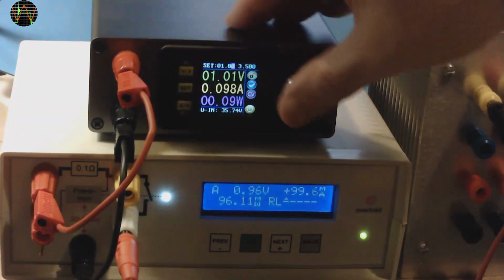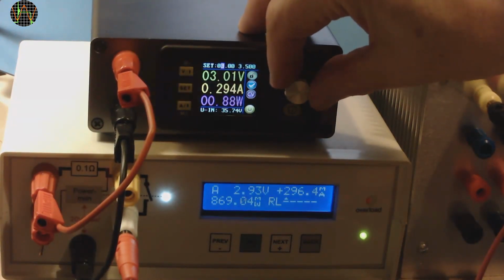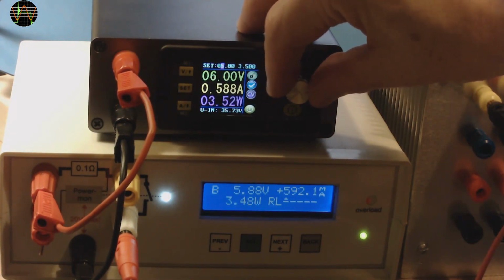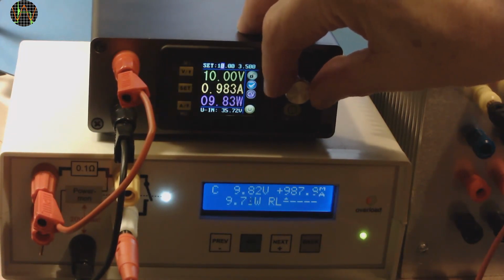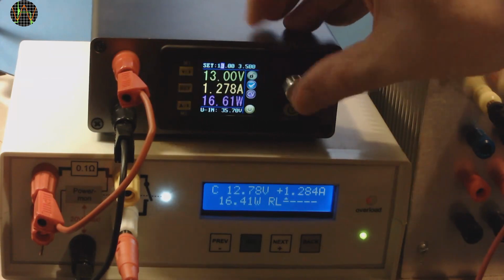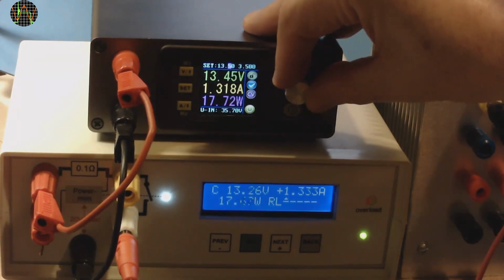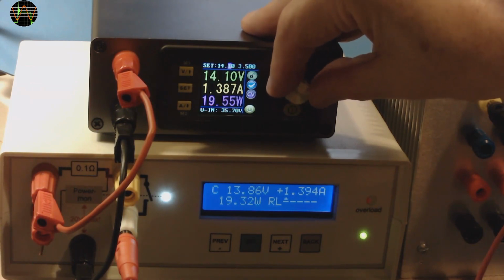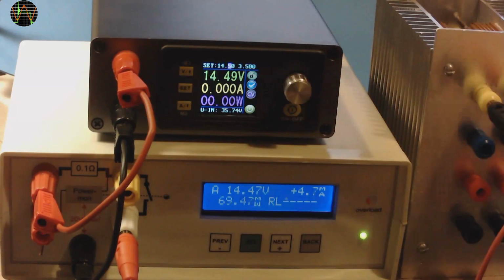I'm now increasing the voltage. The difference in voltage between the power supply and the power mon are due to voltage drops, and as the L in the status shows, power mon is currently configured to measure the voltage over the load, not the supply. There, the relay triggered. I was a bit hasty in cranking up the voltage, so we overshot the 14.2 volt limit somewhat. You can see the high volt status is blinking.